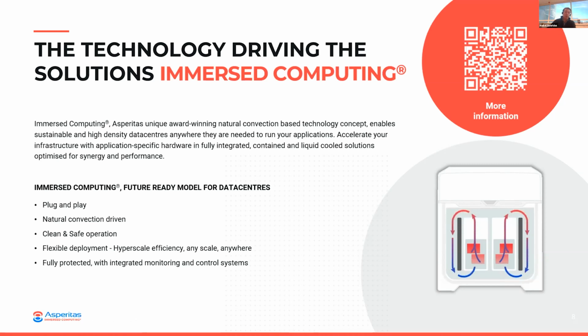Because we don't mix the environment of the whole basin of dielectric fluid, we don't need to maintain one temperature to keep all of the components cool at the lowest requirement we see in the server - could be 20 or 32 degrees Celsius. We don't need to do that. It's self-managed, and there's a temperature layering within the system where there can be a delta within a basin. That allows for warm water cooling, which is a great advantage. In some circumstances, we have seen cases where the requirement is to cool with ambient temperatures of 48 degrees Celsius even - quite a high requirement that can be done with natural convection based cooling.